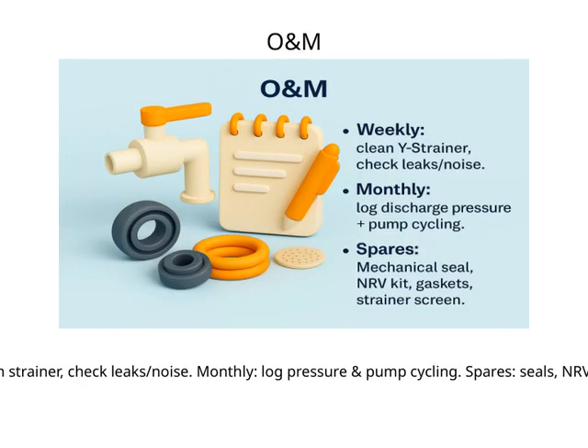Now, let's talk about our operation and maintenance routines. On a weekly basis, it's important to clean the strainer to prevent any buildup that could hinder performance. We also need to check for leaks and any unusual noises, as these can be early indicators of potential issues. Moving to the monthly tasks, we log the pressure readings and monitor pump cycling. This helps us spot trends or irregularities over time, ensuring everything stays within optimal ranges.